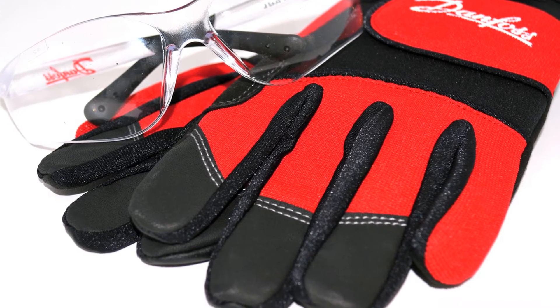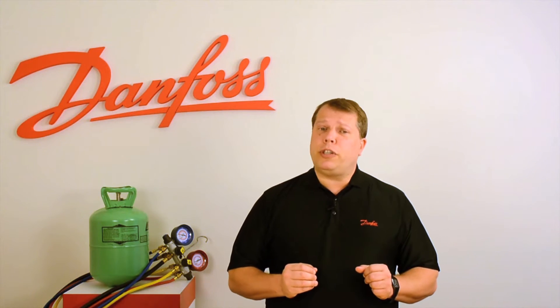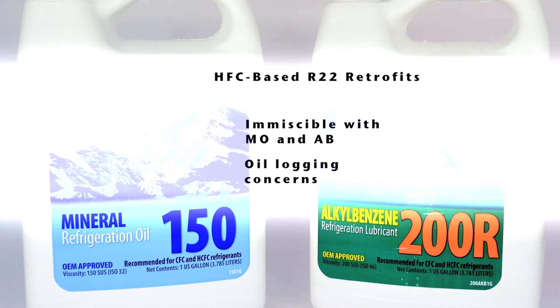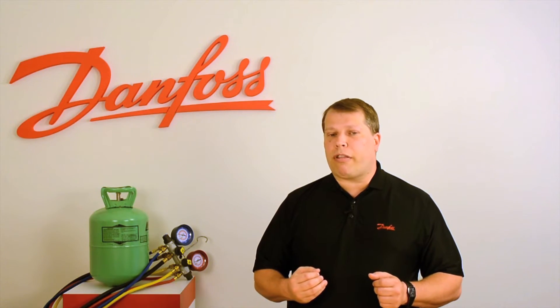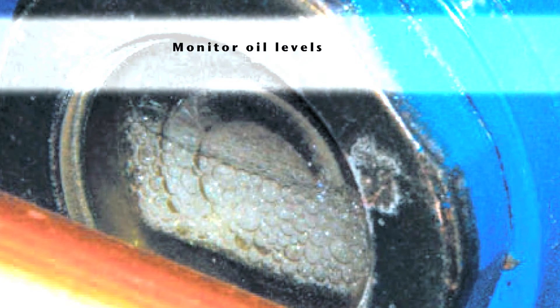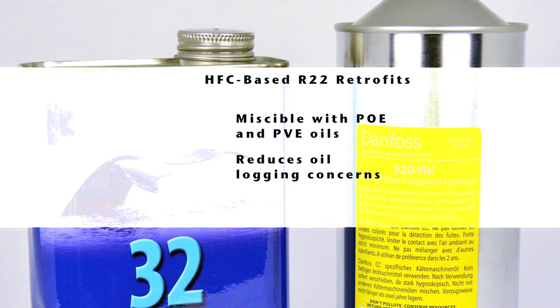Always be sure to use personnel protective equipment. It's important to understand the types of refrigerants you'll be working with. R22 retrofits are non-ozone depleting HFC-based refrigerants. These products are mostly immiscible with the mineral oil or alkyl benzene lubricants typically found in most R22 systems. While some systems may perform acceptably using the original compressor lubricant, the use of immiscible refrigerant-oil combinations may lead to problems with oil return and oil logging in many applications, such as systems with receivers or process chillers subject to low flow rates. This could potentially lead to compressor failure or reduced system performance. Therefore, monitoring of compressor oil levels and circulation rates is critical.